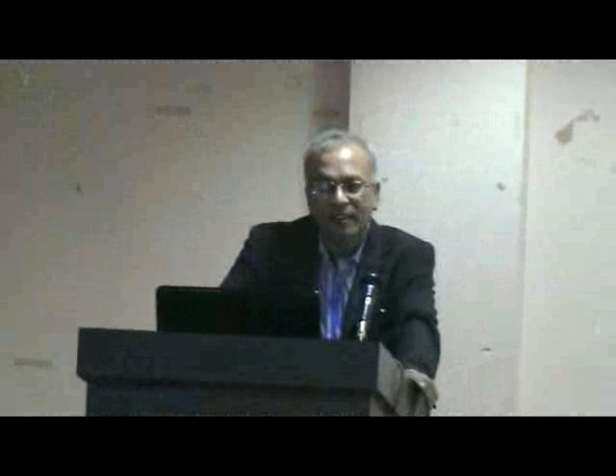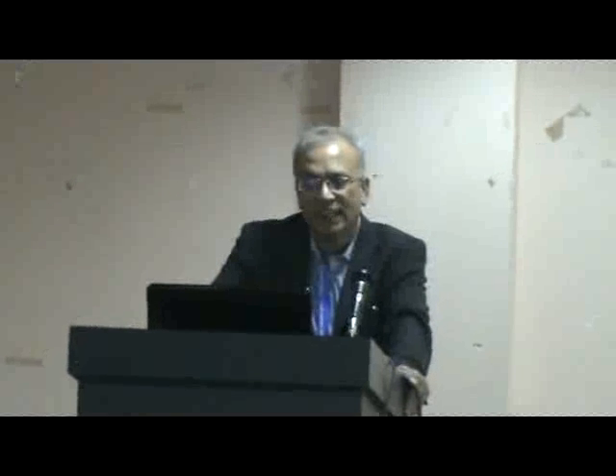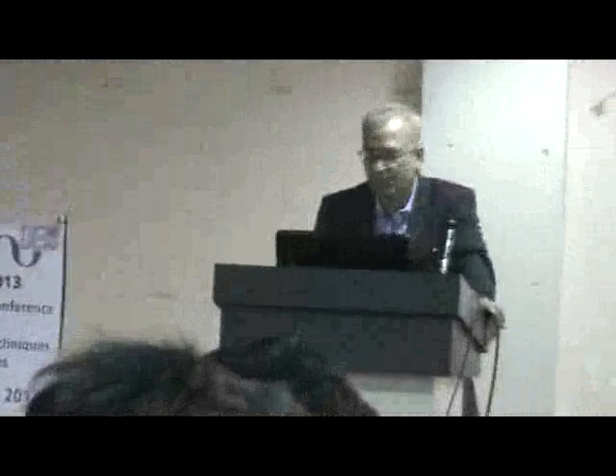The advantages in low voltage systems over bare conductor systems are substantial reduction of line outage, improved reliability of the system, reduction of cost towards energy not supplied, safety of people and cattle, reduction of leakage current, reduction of general bushfire, and conductors being bundled together, no phase-to-phase or phase-to-earth clearance is required. There is also reduction of right-of-way, which is a very serious issue all over the world and has become so in India recently, obviation of tree trimming and reduction of maintenance and its cost.